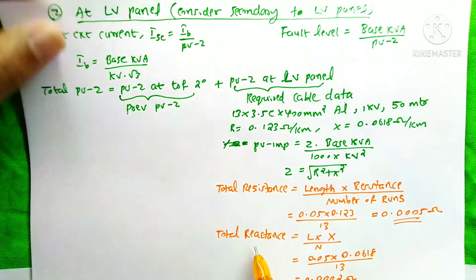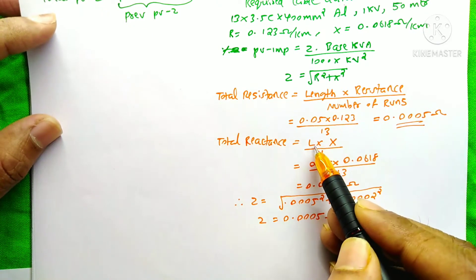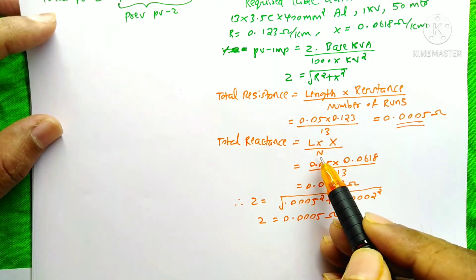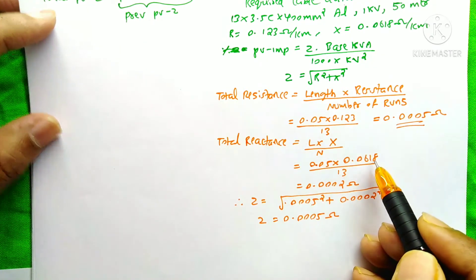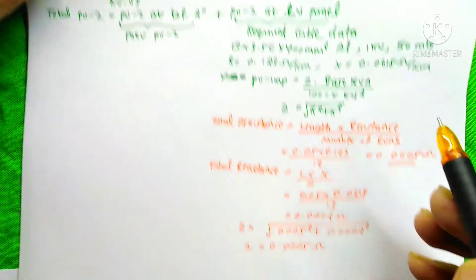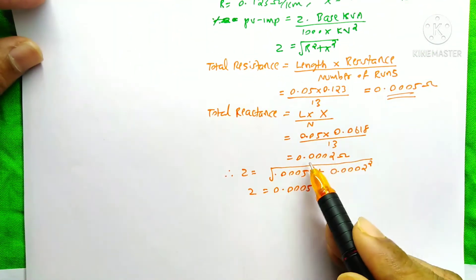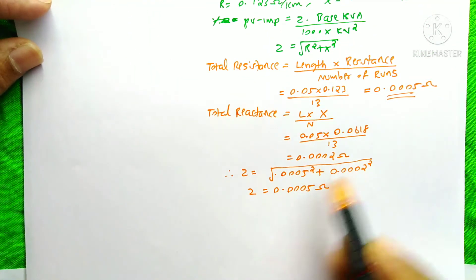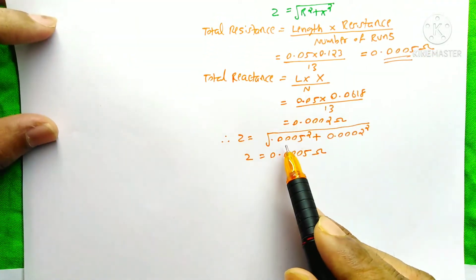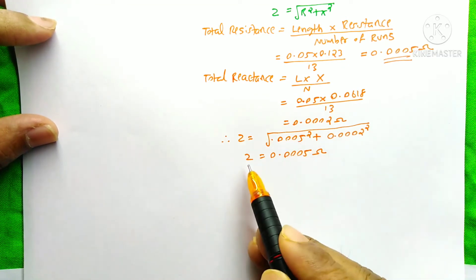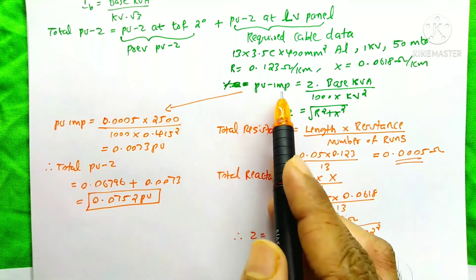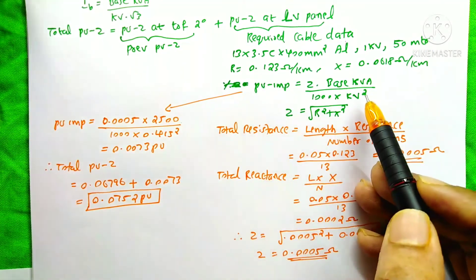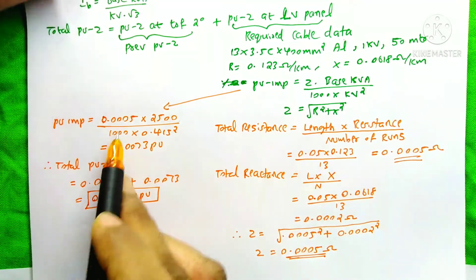The total reactance equals length of cable into reactance of cable divided by number of runs: 0.05 km into 0.0618 Ohm/km divided by 13, giving 0.0002 Ohms. The impedance Z equals root of 0.0005 squared plus 0.0002 squared, so Z equals approximately 0.0005 Ohms. Now we find the per unit impedance at the LV panel using Z into base kVA divided by 1000 into kV squared.